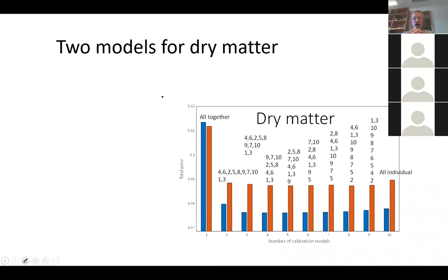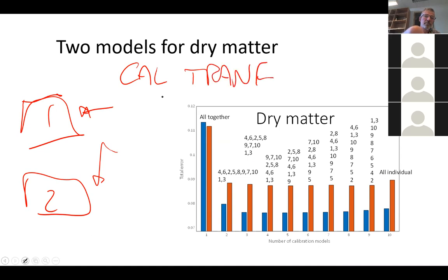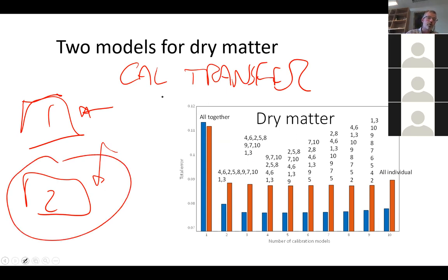So okay, and then there's a question if there's also a way to overcome instrument variations. So for example, if I have instruments that are different, sometimes we bought the same 2 versions of the same instruments, but it turns out that if I build the model on one and predict with the other, we don't really get nice predictions. And sometimes you can use what is called calibration transfer, which is maybe not the most fortunate name, to change the 2 measurements to look like 1 measurement. And definitely this could be used for that as well.